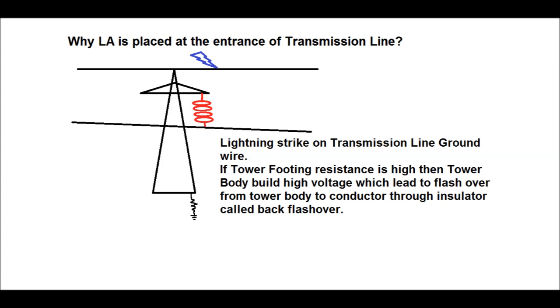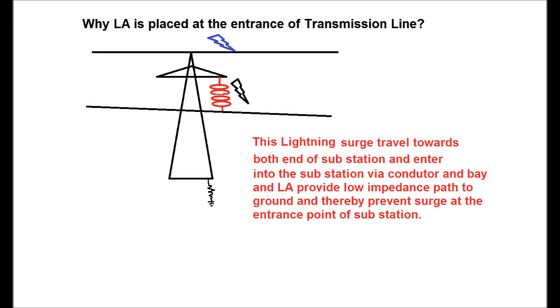If the transmission line tower footing resistance is high, then the tower body builds up high voltage, which leads to flashover from the tower body to the conductor through the insulator. This is called back flashover. This lightning surge then travels towards both ends of the substation and enters the substation by the conductor. LA is provided at the entrance of any bay so that the lightning arrester provides a low impedance path for any overvoltage, thereby protecting the substation equipment.